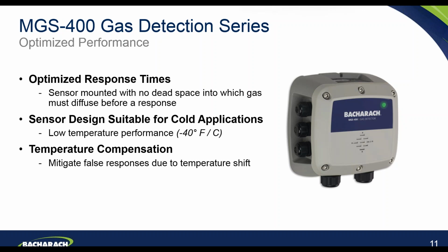In addition, a huge step forward with regard to particularly the semiconductor sensors that the 400 series utilizes for HFCs and HFOs, for example. One of the inherent downsides from a technological perspective with semiconductor sensors is that they can be prone to fluctuations with temperature shifts. So that potentially can and has in the past created false responses. So for example, a typical classic example is on defrost cycles, where you go through a defrost cycle, the temperature shifts significantly, and the semiconductor sensor can go into alarm.